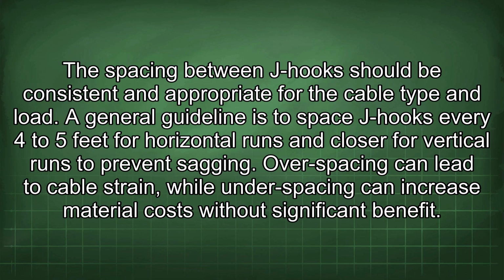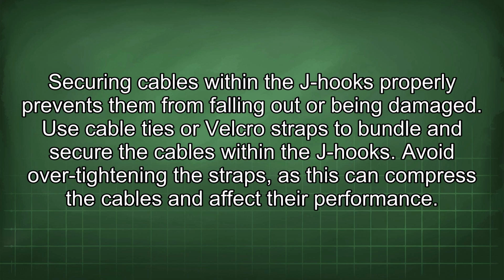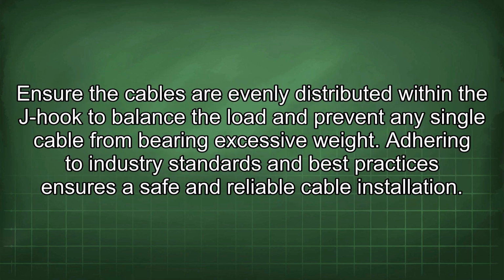Overspacing can lead to cable strain, while underspacing can increase material costs without significant benefit. Securing cables within the J-hooks properly prevents them from falling out or being damaged. Use cable ties or Velcro straps to bundle and secure the cables within the J-hooks. Avoid over-tightening the straps, as this can compress the cables and affect their performance. Ensure the cables are evenly distributed within the J-hook to balance the load and prevent any single cable from bearing excessive weight.